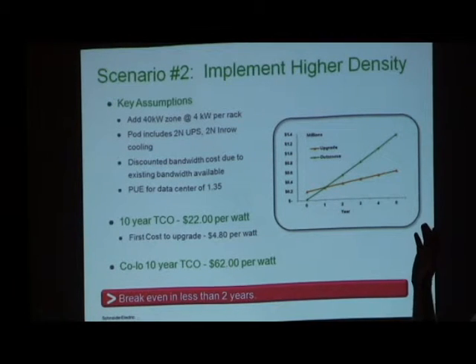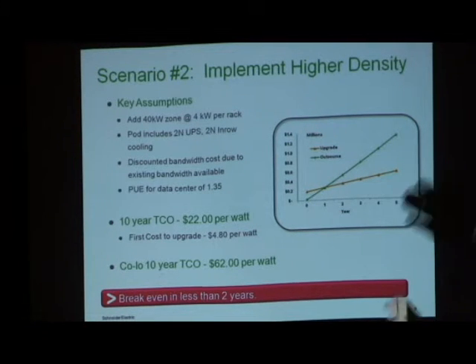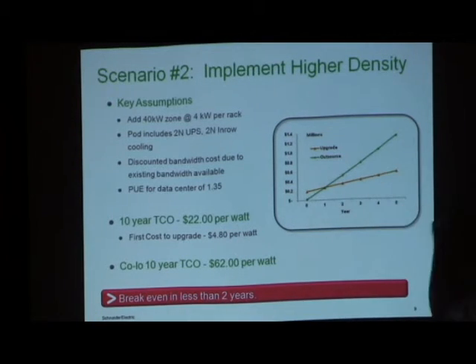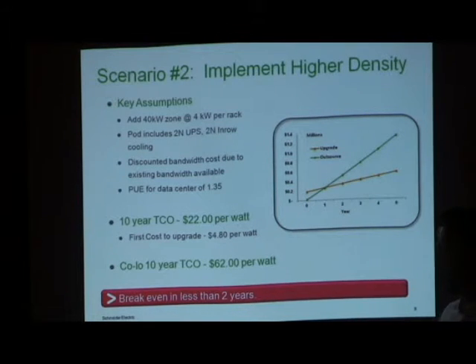Anyone in the room understand PUE? Great, a couple hands go up. PUE is power usage effectiveness, and what that really means is, for every kilowatt going into the data center, how much of that is being used for actual IT computing, versus being wasted on maybe an oversized UPS or oversized cooling unit. So the closer you get to 1, obviously 1 being perfect and unattainable due to physics, that would be every kilowatt of power coming into the data center used for computing and nothing else. So 1.35 is a very healthy PUE. It's actually very attainable. We have data centers here in Utah that have achieved that.